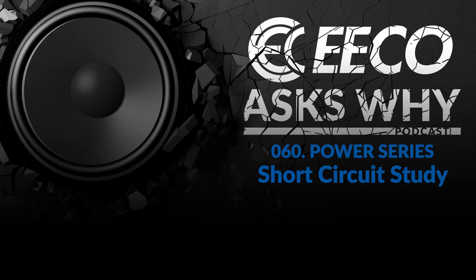And so as that available fault current increases and that protective device is static, there becomes a point where it surpasses the amount of allowable fault current that device can withstand. And so that's what happens over time. We go into these plants, and when they put this system in 8 years ago, it was perfectly fine. But now you're at almost twice the amount of fault current that this protective device or this entire board can withstand. And so at that point, really, the best thing to do is look at replacing that overduty piece of equipment.